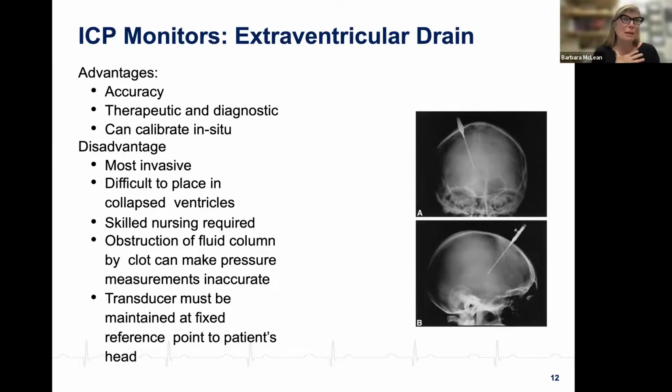At the transducer, depending on what you're doing, you will have a secondary stopcock. That secondary stopcock, one end goes to the pressure tubing, the other end goes to a drain. And what's going to happen is that when my patient's pressure is greater than what I've set it at in my transducer, and again, my purpose here isn't to show you the whole setup, but just to remind you that when you set this monitoring up, you actually set a level above which your patient will drain their cerebral spinal fluid.